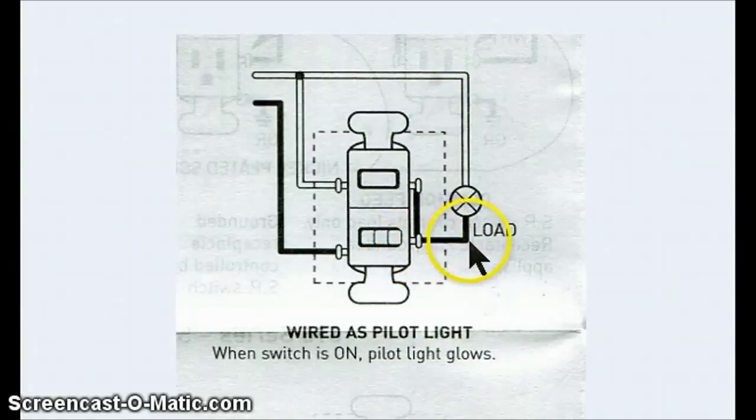You hook the black or the red wire coming from the load, which is your fan, your light, your outlet, whatever, onto this brass screw. The other side of the load already has the neutral hooked onto it. This screw will receive nothing. You can just close it down and leave it closed.